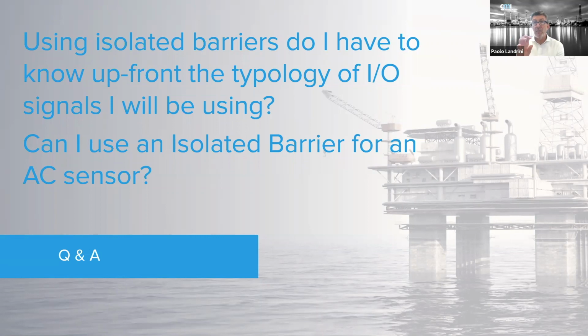Each certificate states which standard they comply with, and as long as you're comparing apples to apples, you can take certificates from different bodies, TUV, DEKRA. But in this case, you have to match the parameters, so let's say the Ui, Uo. This is a question we would have to pose to our certification expert, Roberto, who is not here today with us.